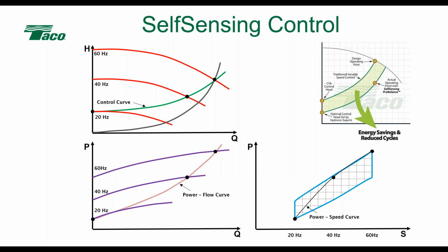And what's going to happen is now we have this true power speed curve that's loaded into the pump and into the controller. As valves start to open and close in the system, what happens is now the pump is not operating on that control curve. The power, speed, and flow don't match. So the controller is going to go, okay, I need to either speed up or slow down to get it back on that control curve. So it's always working to constantly stay on the control curve. As valves open and close, the pump is going to speed up and slow down to stay on that control curve.